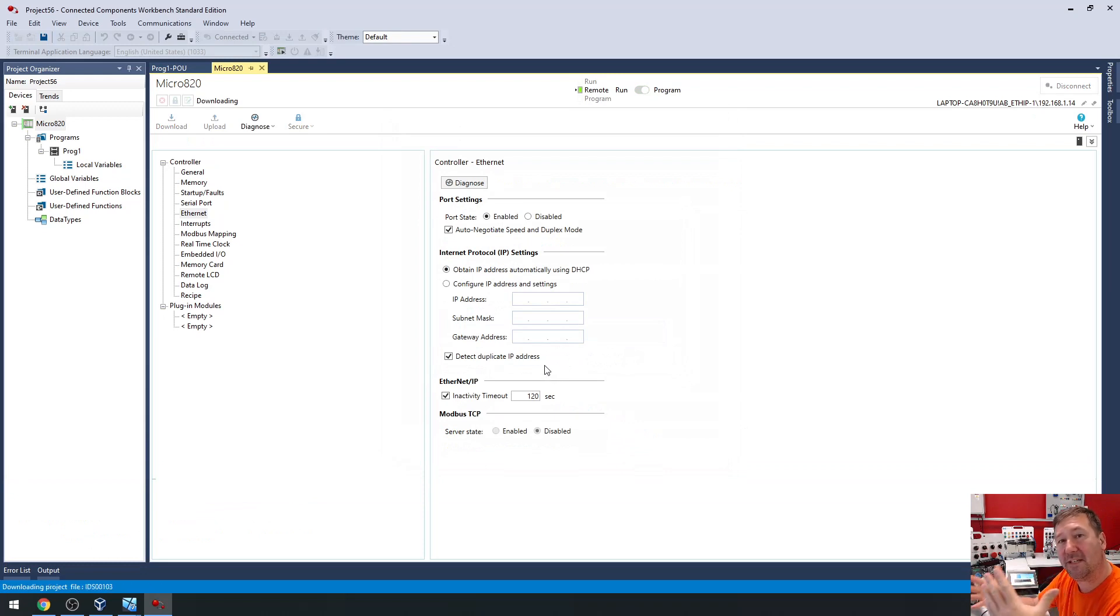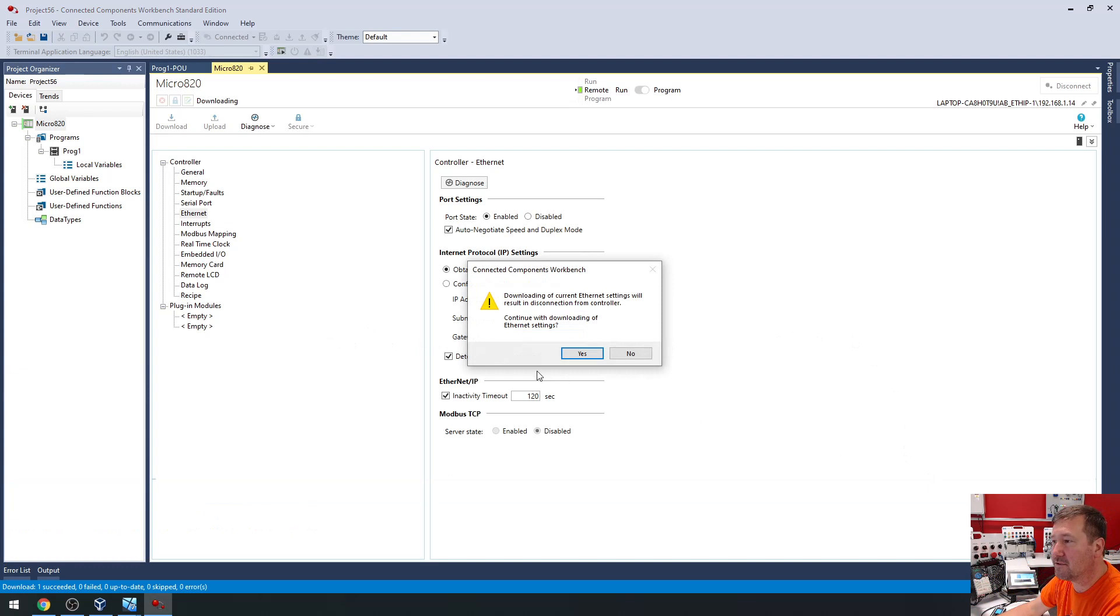It's going to ask to download with project values, and this is the part that's going to trip you up. Typically the next button is 'do you want to put it in and run,' so I've got my finger on the trigger ready to hit the yes button. But if we look at this, it actually says 'downloading current Ethernet settings will result in disconnection of controller, continue with downloading Ethernet settings.' But in my mind I'm just like, yep, I need to hit the run button, so I click yes.